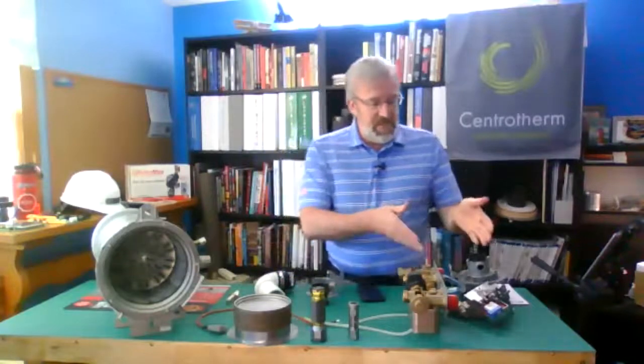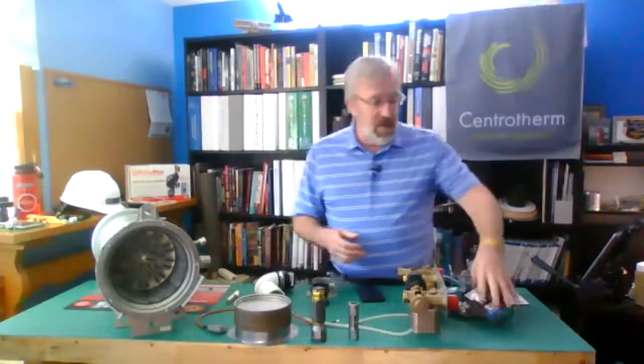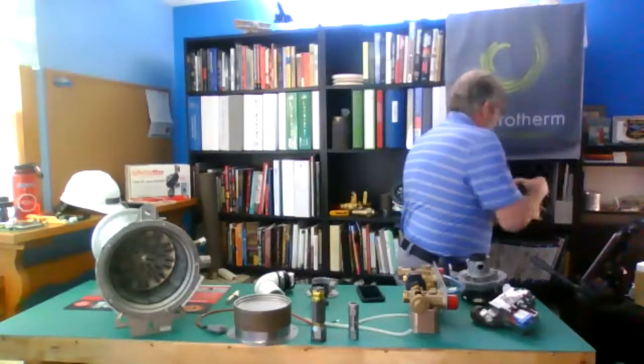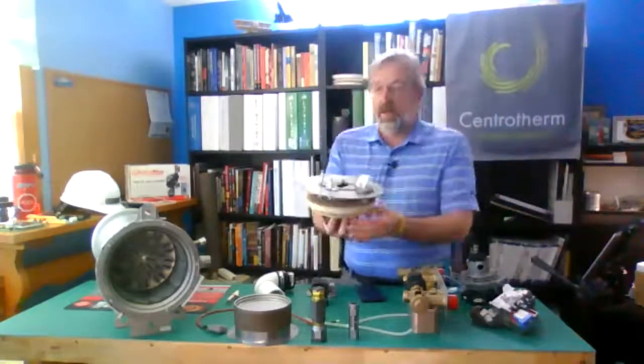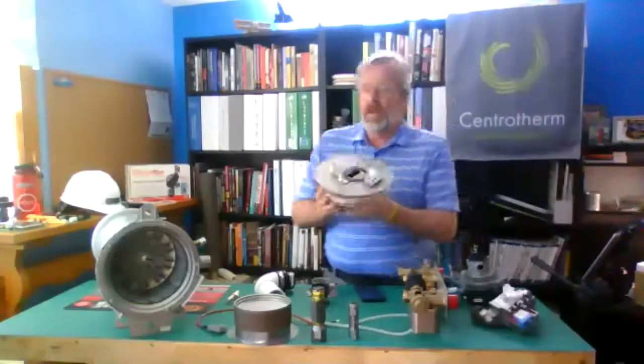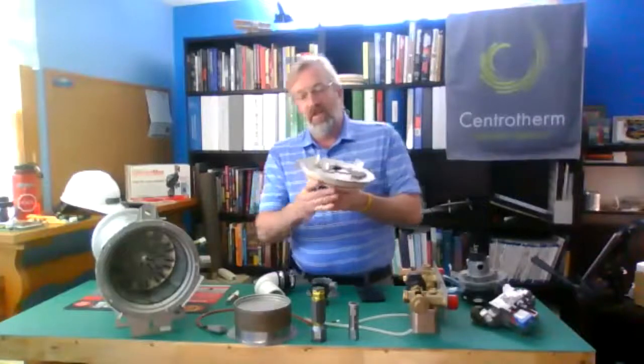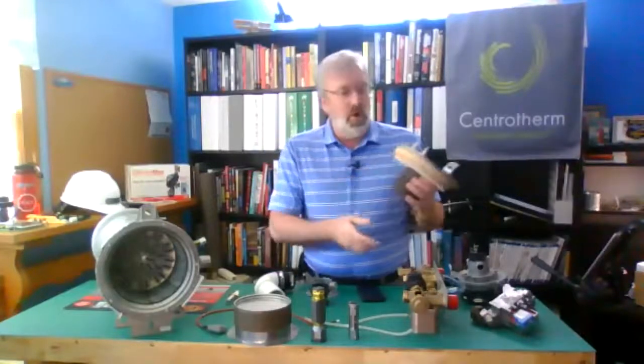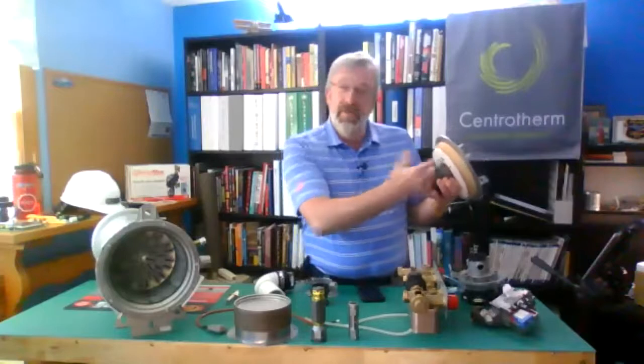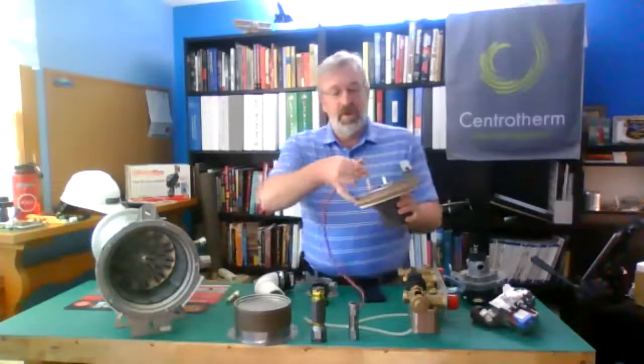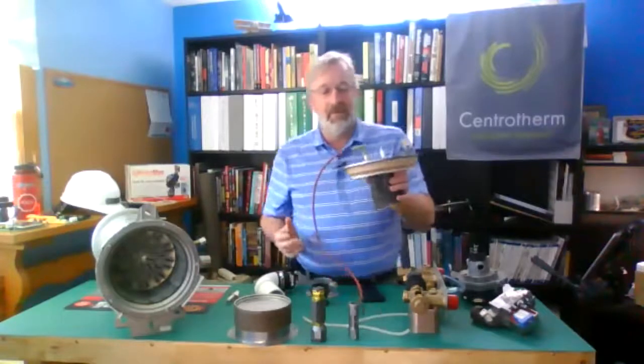So we test that. We've determined we have gas. Gas is coming through. Let's move to our next step in the process. So our next step in the process is, do I have spark? Now, cheating a little bit here, this is the top off a WHB. So difference in a WHB versus a Noble is we add an extra flame sensor in a WH, which we don't in the Noble. But for all intents and purposes, most everything else is the same.